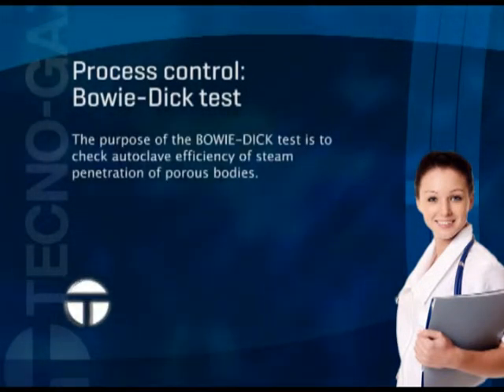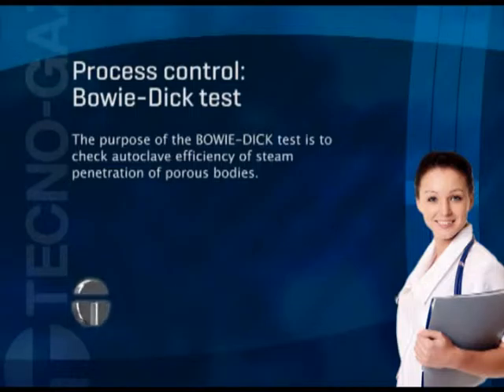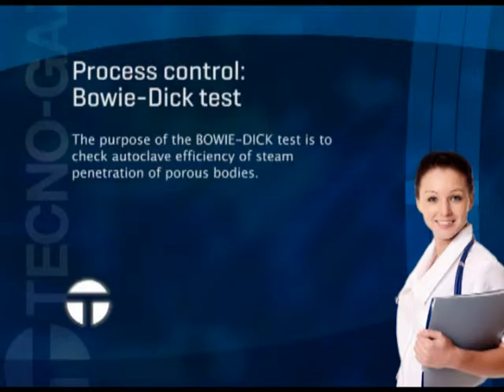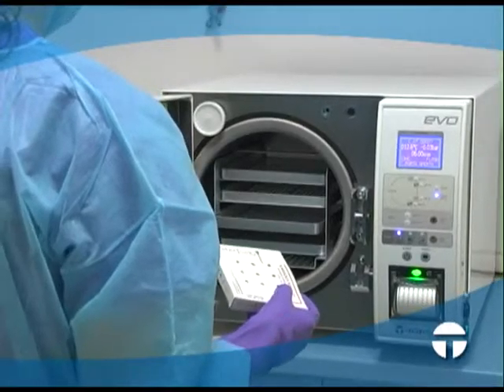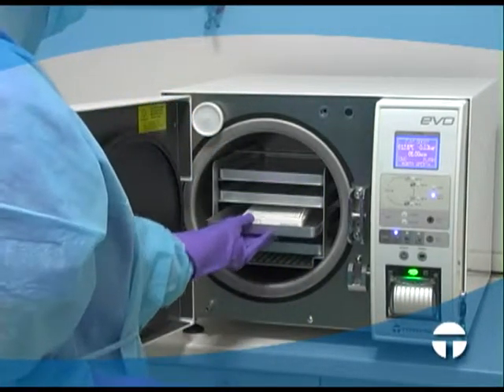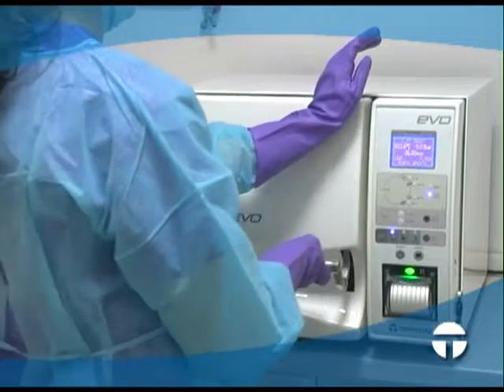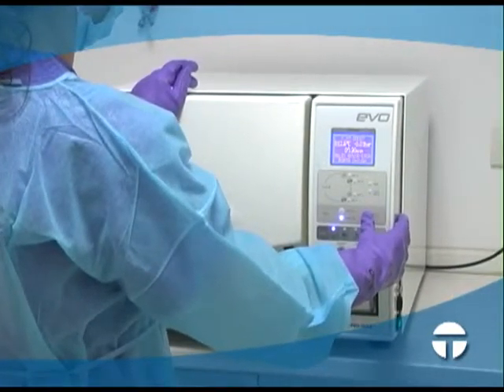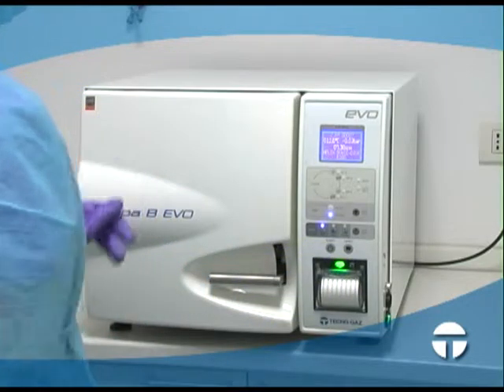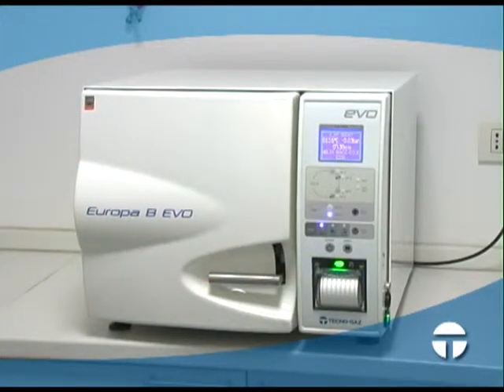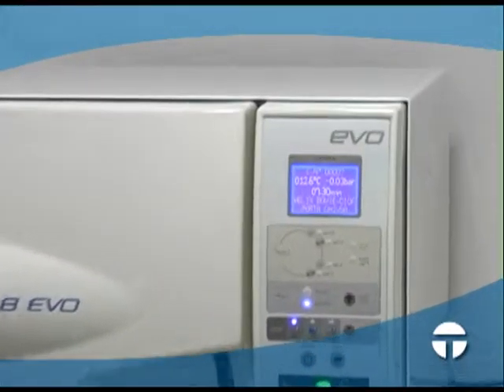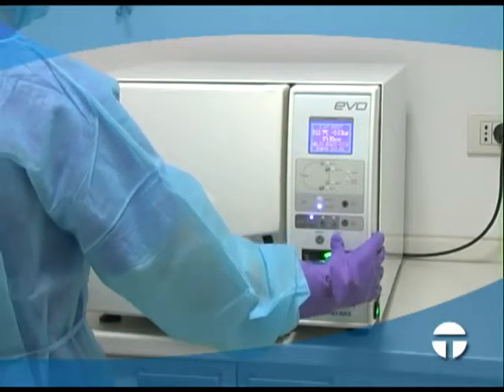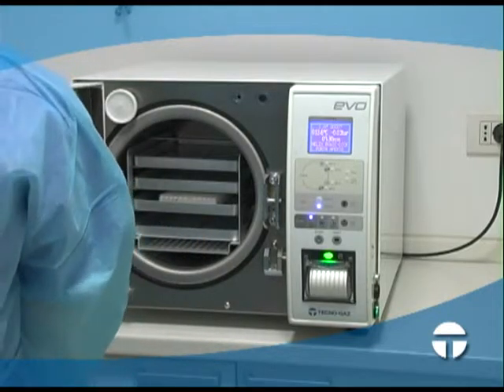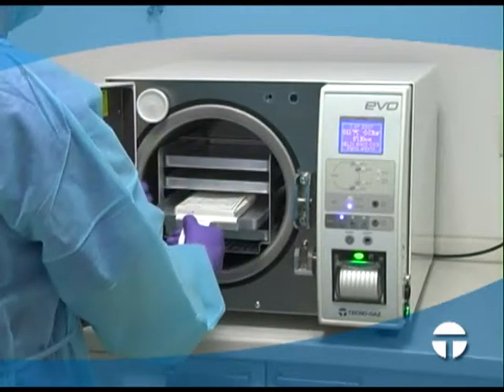Bowie Dick Test. The purpose of the Bowie Dick Test is to check autoclave efficiency of steam penetration of porous bodies. Place the Bowie Dick Test packet on the central tray of the sterilization chamber without any load. Close the door. Select the Bowie Dick cycle and start. At the end of the cycle, remove the packet. Open it and check the results against the internal test sheet.